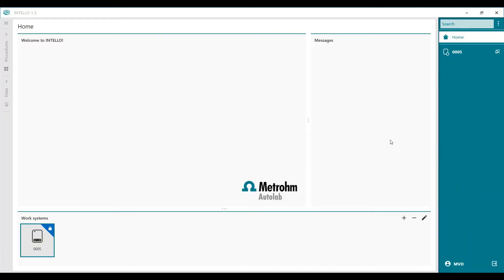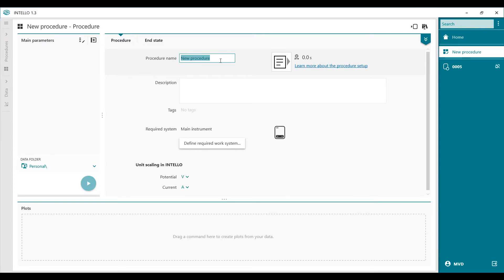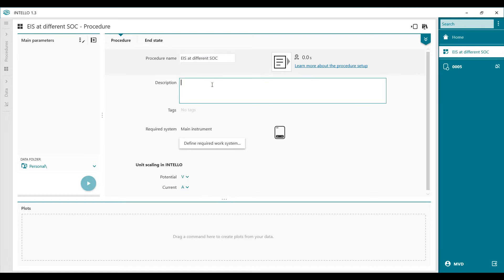We start a procedure from the beginning, so we go to Procedures and press the plus button to create a new procedure. We give it a name — for example, 'EIS measurement at different state of charge.' In the description you can describe your cell; we have a coin cell.